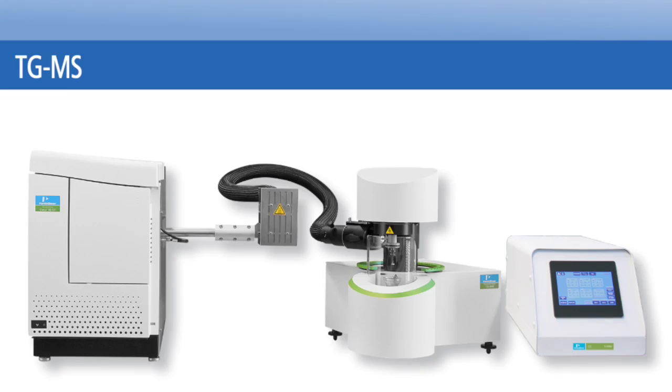If you're wondering about solvates, they would do the same thing in a TGA. The only thing that's tricky is when you don't know what solvent might be present, because you need the molecular mass to calculate the ratios. In which case, you can examine the purge gas emitted from the TGA with a mass spectrometer. This type of experiment is called evolved gas analysis, or EGA.